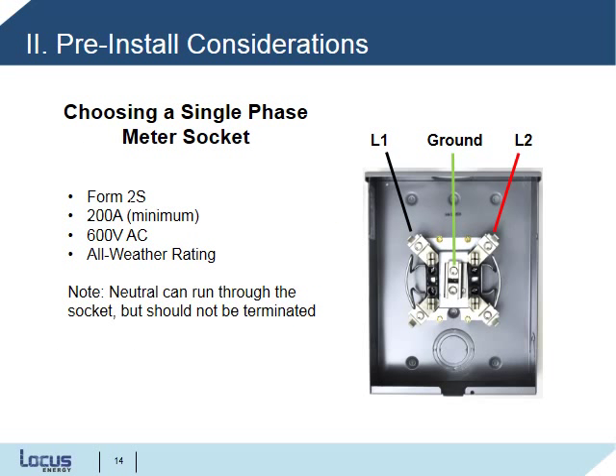The first pre-installation consideration is choosing a single-phase meter socket for the LGate 120. Now these meters will not ship with a meter socket. There are a number of compatible models on the market, but they must meet the following specs. The meter socket should be form 2S, rated to 200 amps minimum and 600 volts AC. We recommend getting a meter socket with an all-weather rating, particularly for outdoor installations. In this diagram, the lug for L1 is on the left and L2 on the right. Ground is found in the middle of this meter socket. Just to note, neutral can be run through the meter socket for the LGate 120, but it should not be terminated.